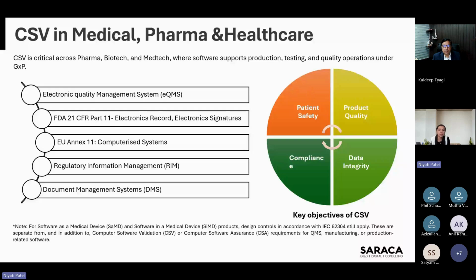And so, for example, for the device software of a SaMD device, you also have to add design controls per the IEC 62304 guidelines. So you often need to balance the validation and the design aspects and the artifacts of design control. The challenge then becomes that not all systems are equal in terms of patient safety, product quality, data integrity or compliance. And historically, CSV has been applied with the same heavy hand across the board. It treats everything the same, and that sometimes becomes inefficient because you're wasting time and energy treating everything the same way. That's where inefficiencies creep in. It becomes heavy, loaded and burdensome sometimes. So we'll unpack how to avoid that as we go through the rest of the presentation.